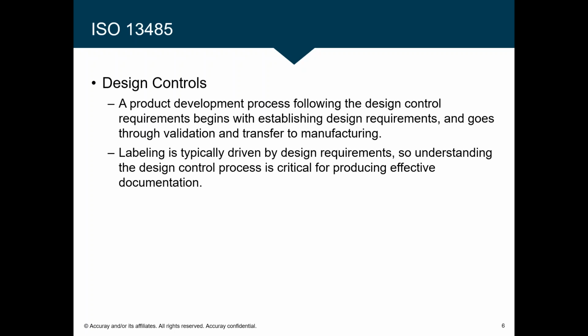At Accuray, as I said earlier, we are part of R&D, so our labeling goes through this process to the T. The requirements for our labeling are derived from system requirements, and those system requirements drive the content. We do verification and validation of the label, and when it's transferred to manufacturing as a part, that label is then active. So labeling is typically driven by design.